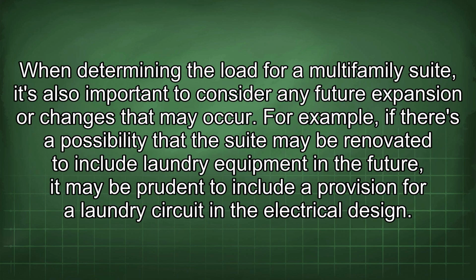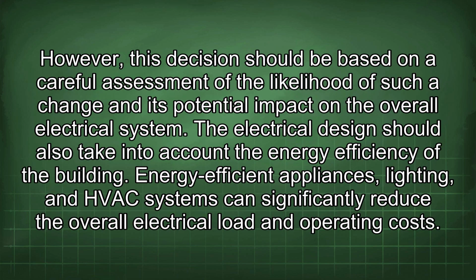When determining the load for a multifamily suite, it's also important to consider any future expansion or changes that may occur. For example, if there's a possibility that the suite may be renovated to include laundry equipment in the future, it may be prudent to include a provision for a laundry circuit in the electrical design. However, this decision should be based on a careful assessment of the likelihood of such a change and its potential impact on the overall electrical system.